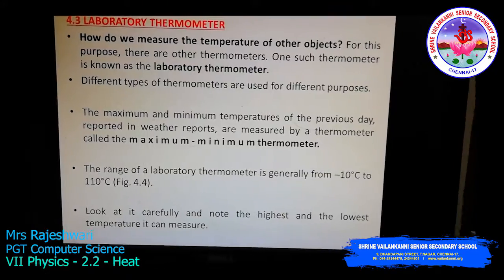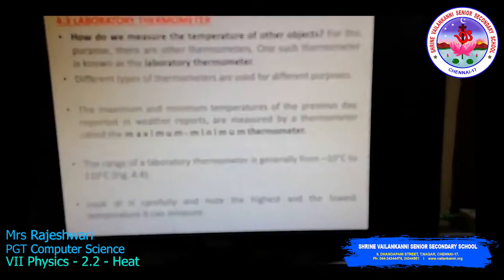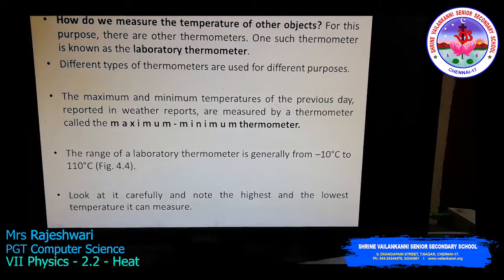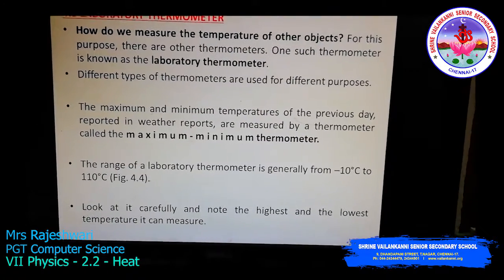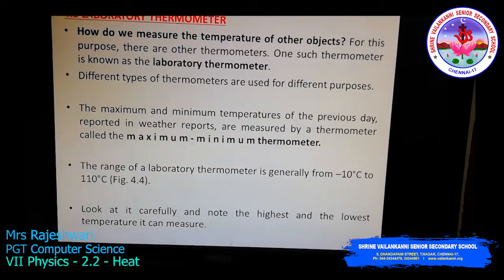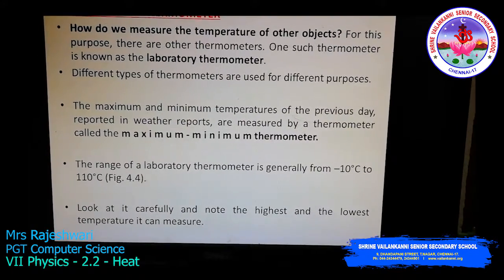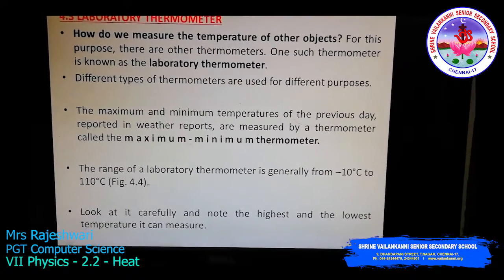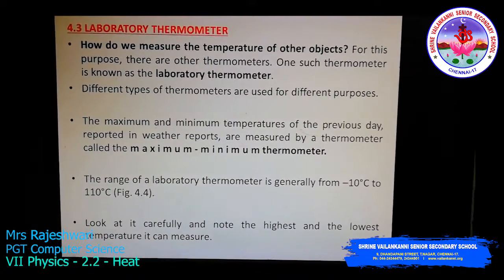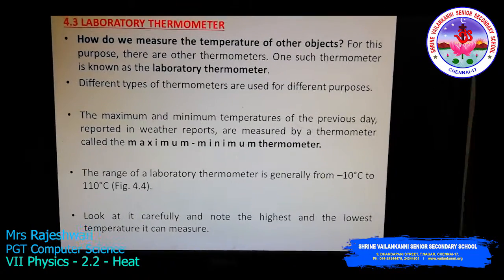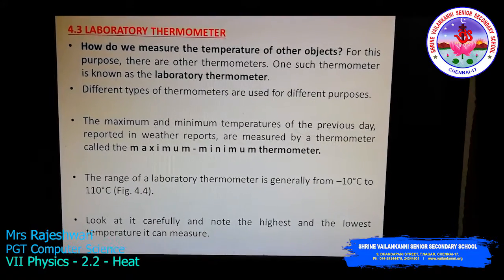That is the reason the clinical thermometer has been set in that range. Whereas in a laboratory thermometer, a particular object may go below 0 degree Celsius or it may go beyond 100 degree Celsius. For example, the boiling point of water may go up to 110 degree Celsius, and a chilled ice cube may have a temperature below 0 degree Celsius. So the laboratory thermometer ranges from minus 10 degree Celsius to 110 degree Celsius. Make a note of the highest and lowest temperatures it can measure.